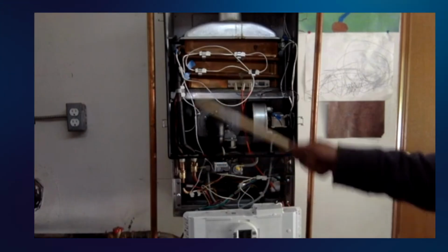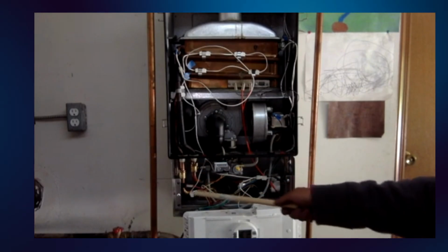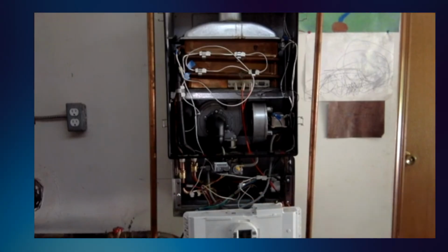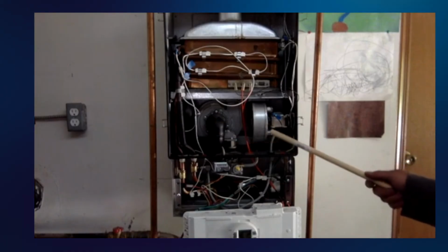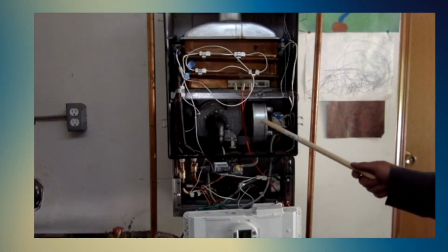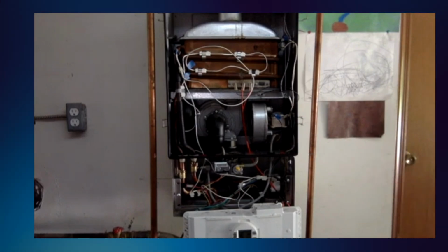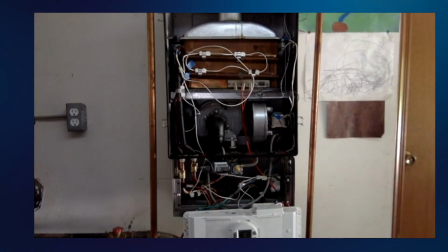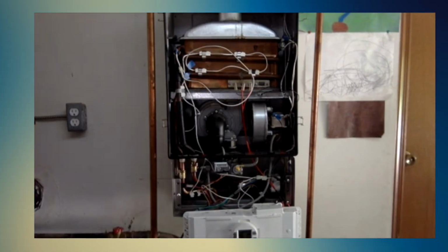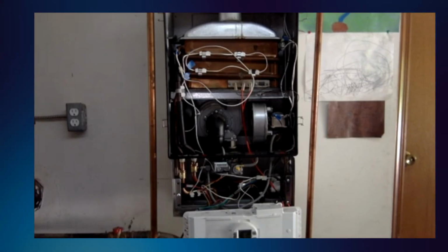If the boiler cannot breathe properly, it may light badly, burn unstably, or fail to detect flame. The sixth possible cause is dirt or buildup inside the heat exchanger or burner area. Over time, some gas boilers and tankless units can collect dust, combustion residue, mineral deposits, or debris in areas related to the burner, heat exchanger, or firebed. When that happens, the appliance may struggle to ignite cleanly or transfer heat efficiently.